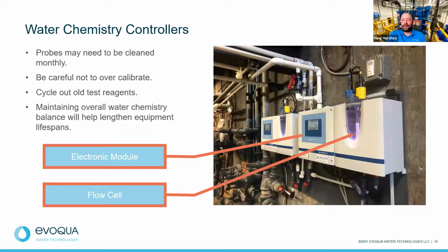So water chemistry controllers: the maintenance requirements vary by body of water, by type of system, by use, by the chemicals, everything that you're using. A couple of key things: be careful not to over-calibrate. A lot of times if you have changing water chemistry parameters, it might be tempting to go in there and change your calibration frequently—please don't do that, do yourself a favor. Cycle out old test reagents, that's another big one. Make sure your test reagents are accurate and providing good water test results, and double check everything, using those numbers to calibrate too. Really maintaining the overall water chemistry balance helps all of these systems last longer and function the way they're designed. That comes into play for all the different components in the mechanical room.